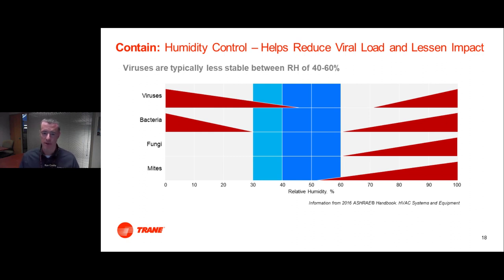Well, it's been well known for quite some time that viruses are more stable at low humidity levels than they are at higher humidity levels. The typical sweet spot has been 40 to 60% relative humidity. The SARS-CoV-2 virus that causes COVID-19 is no different. If you have 25% relative humidity at 70 degrees, you're going to have about 50 times the amount of active virus remaining after 5 hours than if your space is at 50% relative humidity.